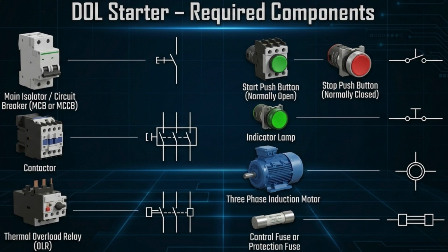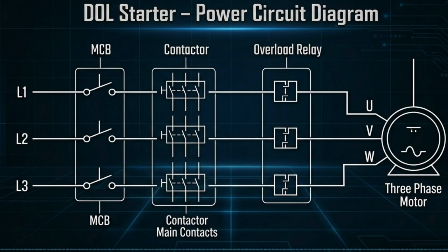In this slide, we are looking at the power circuit of a direct online starter, commonly known as a DOL starter. This is one of the simplest and most widely used methods for starting 3-phase induction motors. As you can see in the diagram, the power supply comes from a 3-phase source labeled L1, L2, and L3. These 3 phases carry electrical power from the main supply towards the motor.